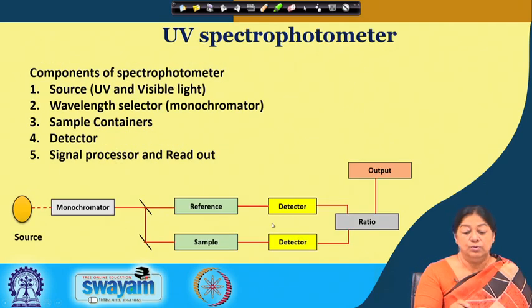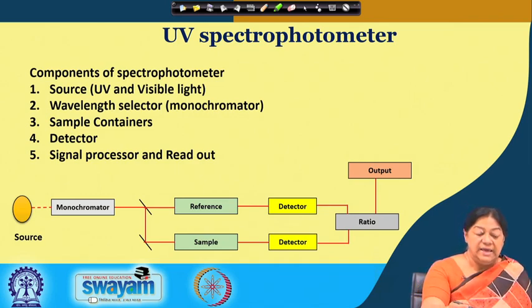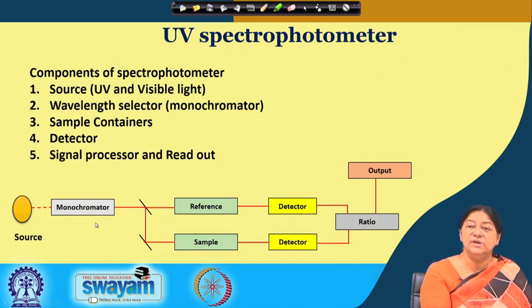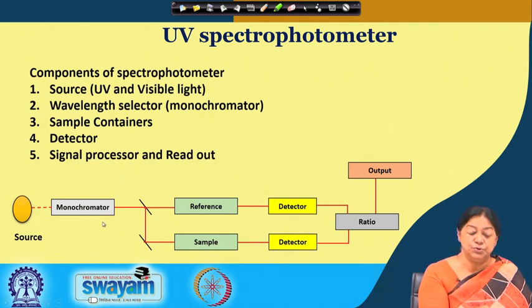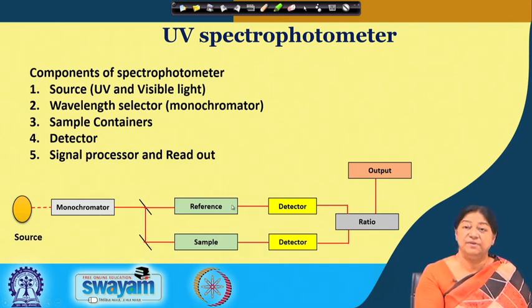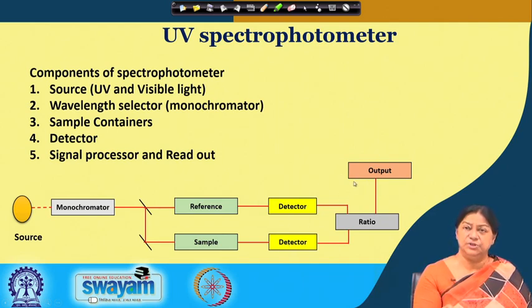When we look at the UV visible spectrophotometer, it has a source, a monochromator which selects a wavelength, a sample and a reference, a detector, and an output. The wavelength selected will depend upon our sample; for proteins, a specific wavelength will tell us whether we have a protein solution or not. From this information we will be able to determine the absorbance of our sample.